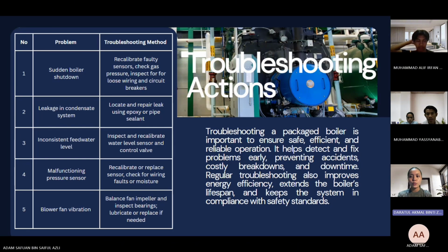For sudden shutdown, we focus on recalibrating the control system and checking circuit components. For the second one, leakage in the condensate line was traced and sealed at joints and piping system. To solve feed water level inconsistencies, we recalibrated sensors and checked the control valve for faults. In the case of pressure sensor fault, recalibration and sensor replacement help stabilize readings. Last but not least, for blower vibration, we balance the impeller and replace damaged components as necessary.